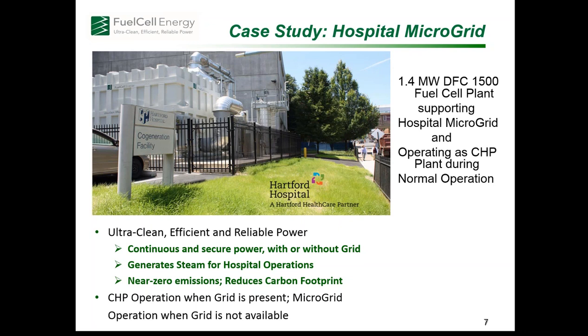So every kilowatt hour it generates is diesel fuel not needed for the diesel generators on site. There's also a small combustion turbine on site generating power along with the fuel cell, the diesel generators, and some solar. They can basically maintain 100% hospital activity in the event the grid isn't there, and seamlessly transfer from one source to the other.